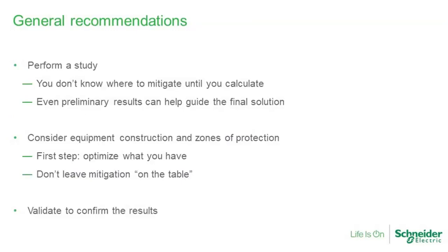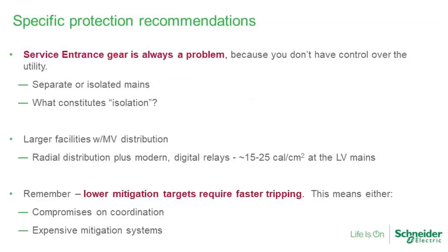the facility. Consider equipment construction and zones of protection. We already talked about that. Validate with calculations to confirm the results before you put the solutions in. Service entrance gear is always a problem because you don't have control over the utility. So maybe separate or isolated mains can be something you look at.